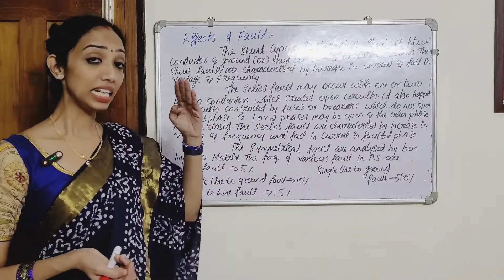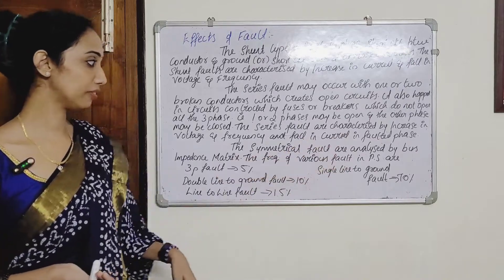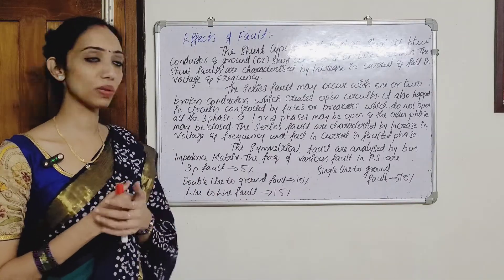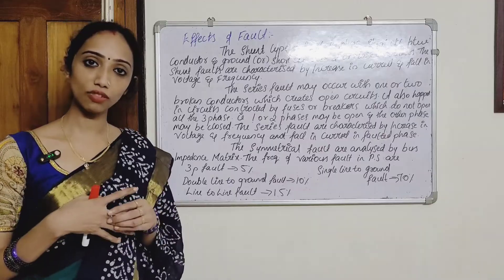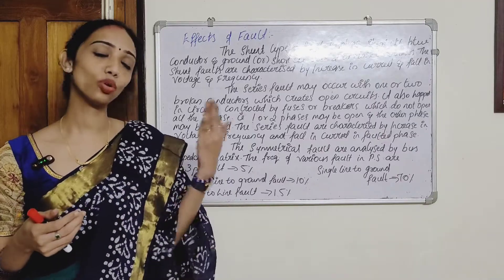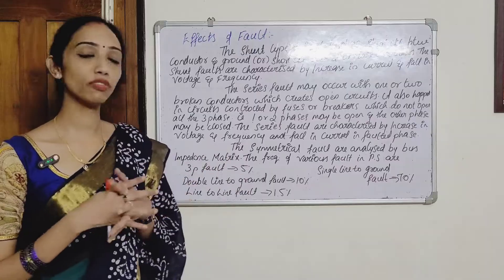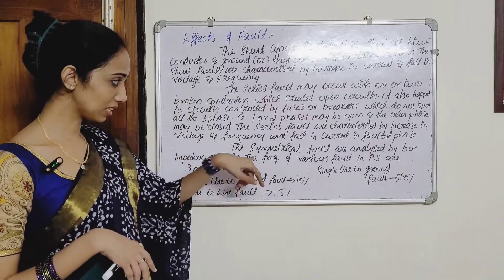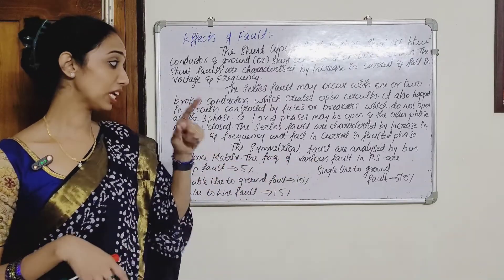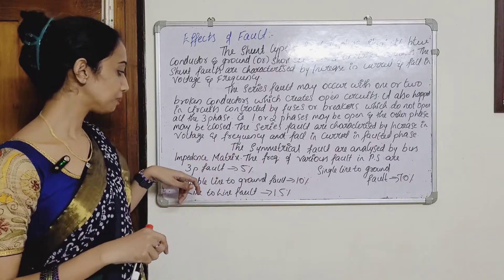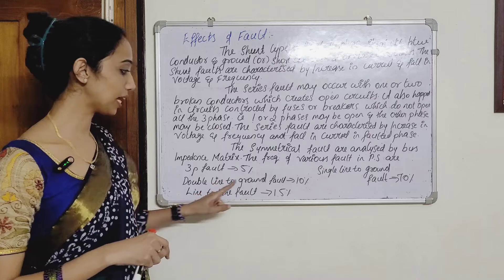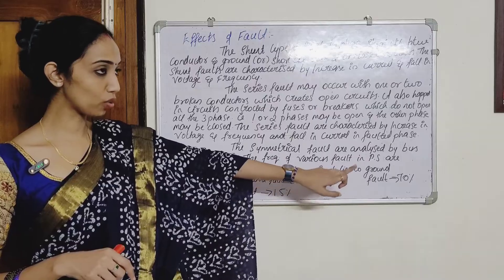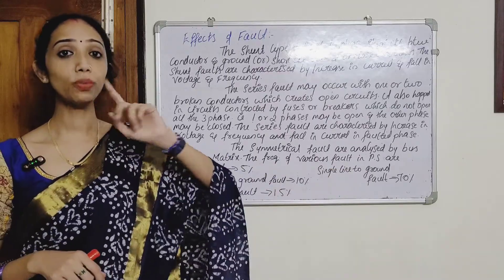Symmetrical faults are analyzed by the bus impedance matrix. Unsymmetrical faults are analyzed by symmetrical components. Regarding fault frequency in power systems: three-phase fault occurs 5% of the time, double line-to-ground fault 10%, line-to-line fault 15%, and single line-to-ground fault 70% — making single line-to-ground the most common fault.